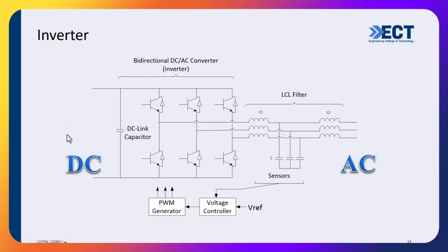The power that comes from a DC source, for example a battery, wind, or PV, gets converted to AC. But because we're switching very fast, the waveform is square, so we filter it using something called an LCL filter, an inductor-capacitor-inductor filter, which gets rid of all the harmonics. Then at the right hand side we get a pure sine wave, exactly like the grid.